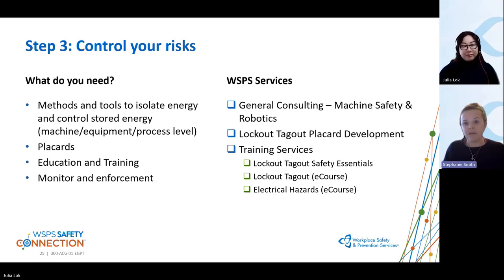Even within those placards, we make references to situations like if your pneumatic gauge is electrical and tied into the electrical panel—if you shut off the electrical, you may shut off your gauge as well, so now you can't verify zero energy. We'll actually change the steps to fit your verification process, so pneumatic may have to get shut off first, then electrical, because of that gauge. That's what our placard service enables us to do.